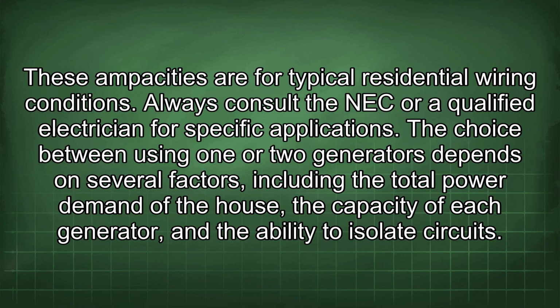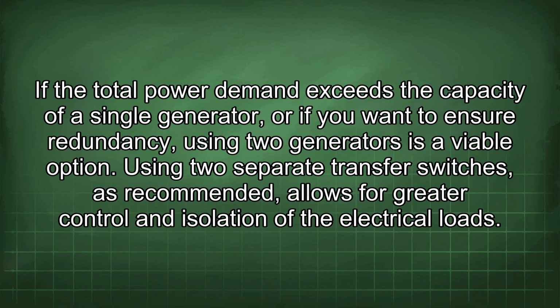The choice between using one or two generators depends on several factors, including the total power demand of the house, the capacity of each generator, and the ability to isolate circuits. If the total power demand exceeds the capacity of a single generator, or if you want to ensure redundancy, using two generators is a viable option.